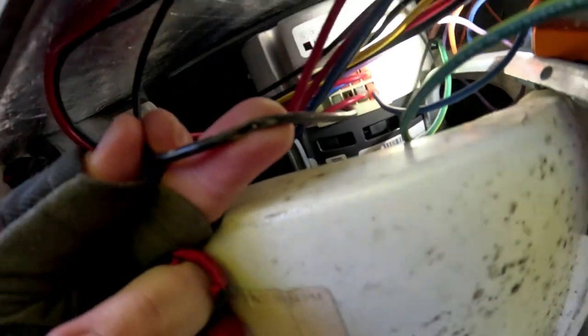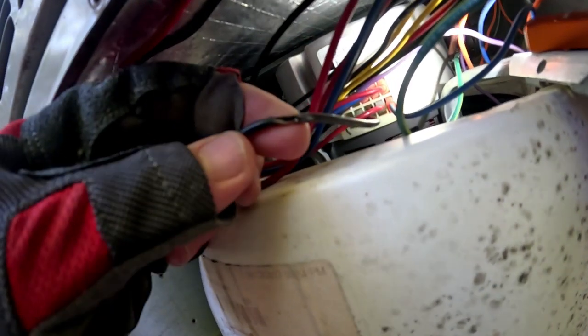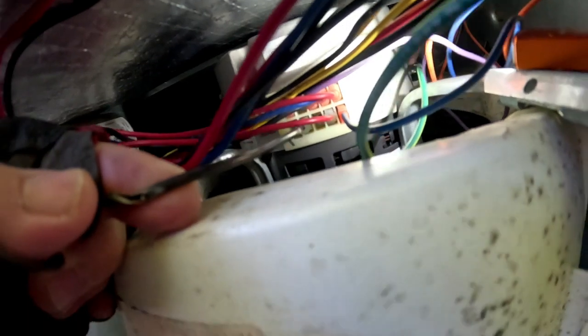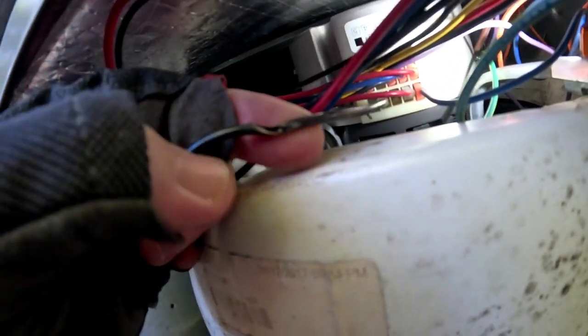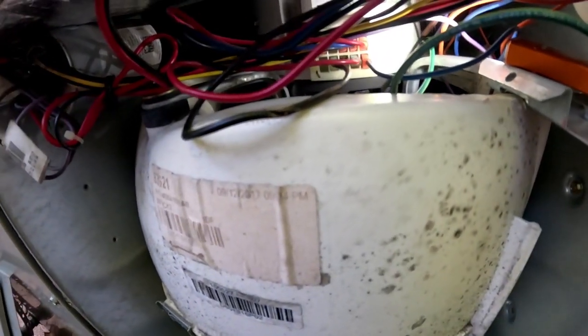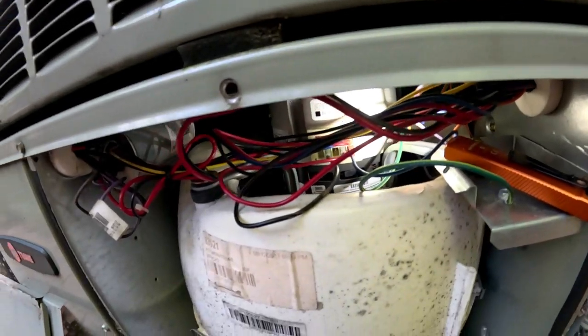And the wire got chopped up, so I'm gonna wire nut that real quick. Actually, I can put a new stake on it because it plugs into the side of the motor. Let's put a new stake on that and then see if we can get this motor to run. Hopefully it's, we'll see. I'm gonna recommend a new motor, but we'll see if it'll still come on and run.